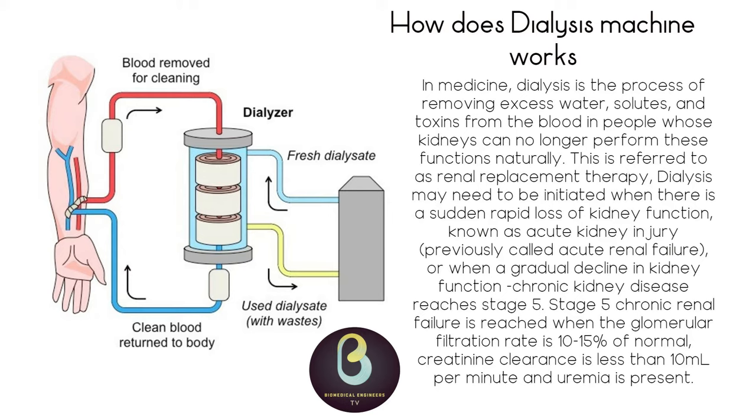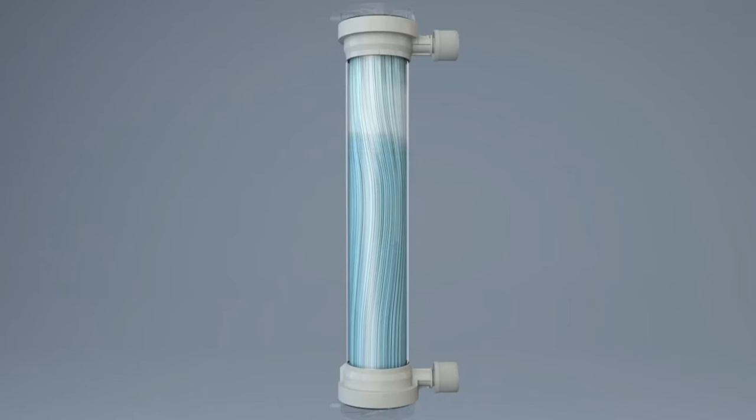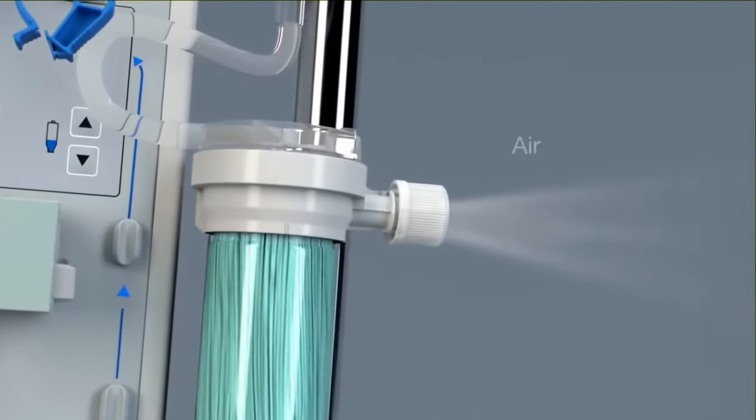Air bubbles in the dialysate cause the blood leak detector and the conductivity detector to malfunction. They also block part of the dialysate pathway, increasing channeling and masking parts of the membrane surface area. The heated and deaerated product water is then mixed with the concentrate to produce dialysate.